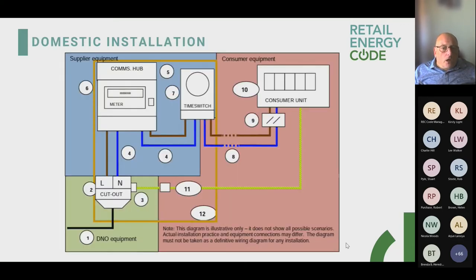So just for defining, on a standard customer's equipment, who's responsible for what? The incoming supply is the responsibility of the distribution network operator. If you see items 1, 2, and 3 listed there, you've got your incoming cable, your cutout, your fusing, your live side and neutral side, and the earthing. The earthing is the distribution network operator's responsibility. Coming off the top side of the cutout, the brown cable's live, the blue cable's neutral.